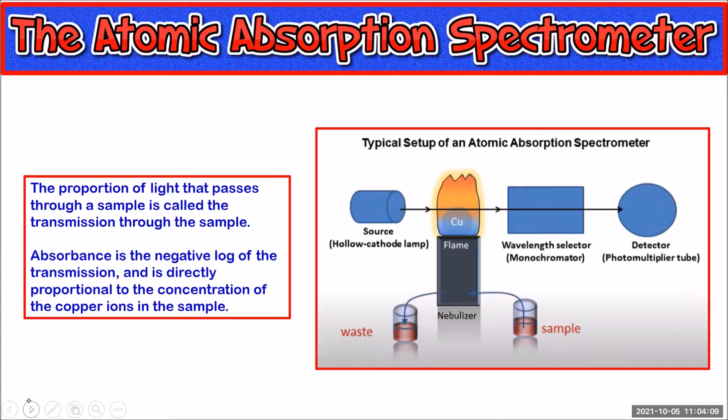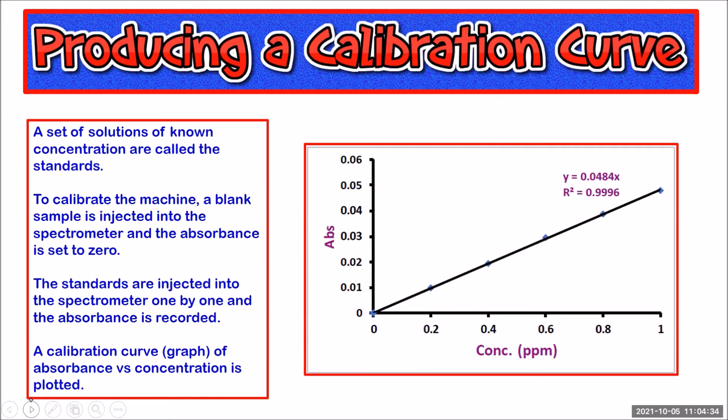The proportion of light that passes through the sample is called the transmission. Now absorbance is the negative log of transmission and absorbance is directly proportional to the concentration of the copper ions in the sample. You need to make a set of solutions of exactly known concentration. So if we were doing a copper analysis, you'd need to make a set of solutions with copper ion concentrations in this graph here of 0.2, 0.4, 0.6, 0.8 and 1 parts per million. Parts per million is also milligrams per liter.